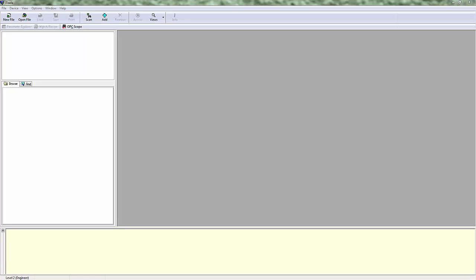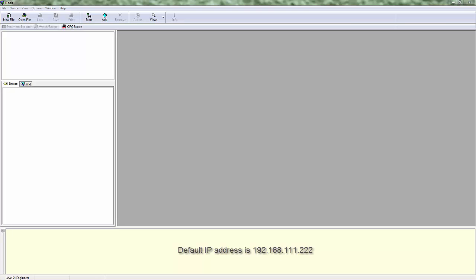From a hardware perspective, we need to make our computer communicate with the IP address of the Eurotherm device. Now out of the box, Eurotherm has a default IP address of 192.168.111.222. That is an internal IP address — chances are something you're not utilizing within your own network.